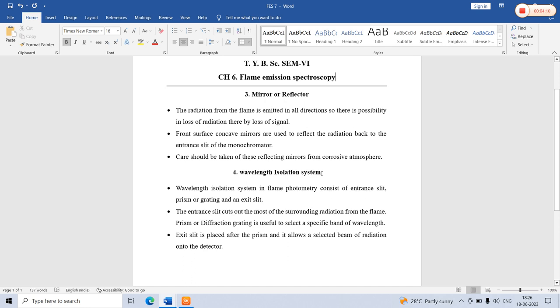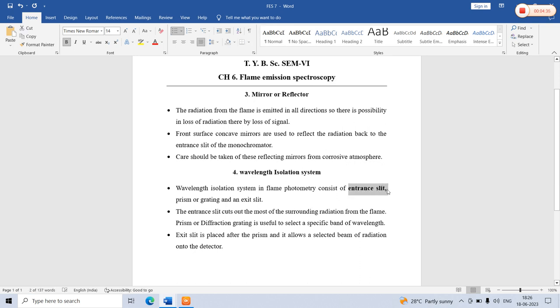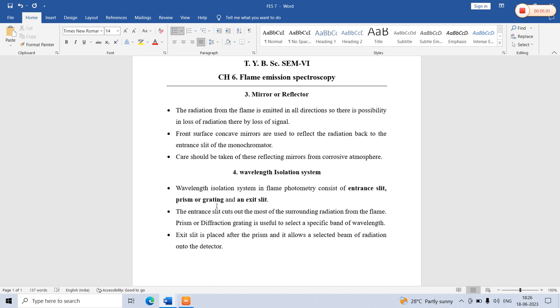The wavelength isolation system is also called the optical system of flame photometry or flame emission spectroscopy. It consists of three components: an entrance slit, a prism or grating, and an exit slit. The role of the entrance slit is that it cuts out most of the surrounding radiation from the flame. The flame gives a tremendous amount of radiation, and the entrance slit removes most of this surrounding radiation.